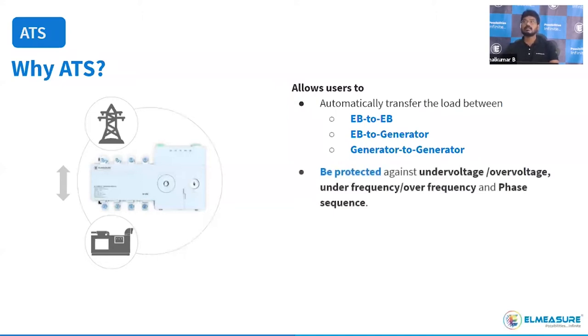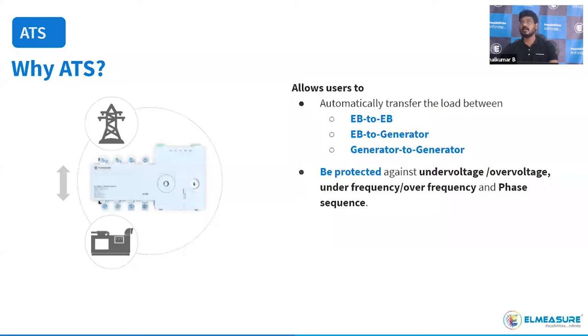Normally in the market, competitors provide only the motorized changeover with no in-built protection. But Elmeasure designs our product with an in-built microprocessor-based controller. The controller monitors the incoming healthy source and, if any fault condition like under-voltage, over-voltage, under-frequency, or over-frequency occurs, the ATS will initiate transfer to the backup source.